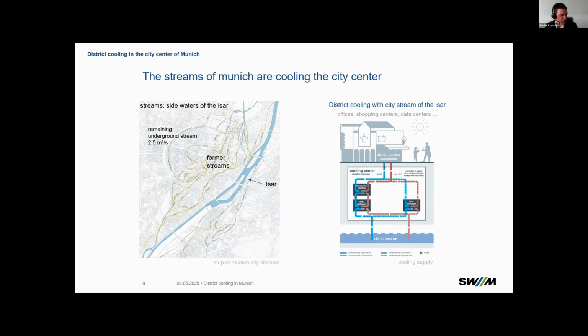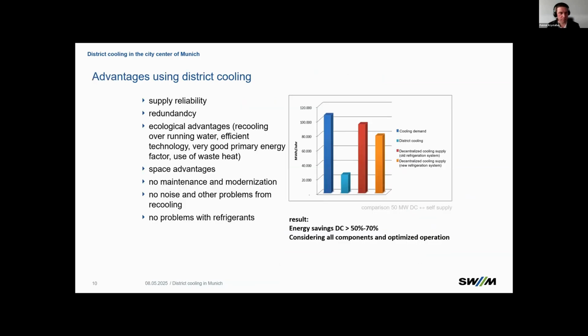So we have a primary factor of around 0.3, which is very good, and the customers accept that and use it for their buildings. Yes, a technically generated cold, and in the winter time, direct cooling. As I said, there are many advantages, and one main advantage is the ecological one over the running water, direct cooling, and so on.